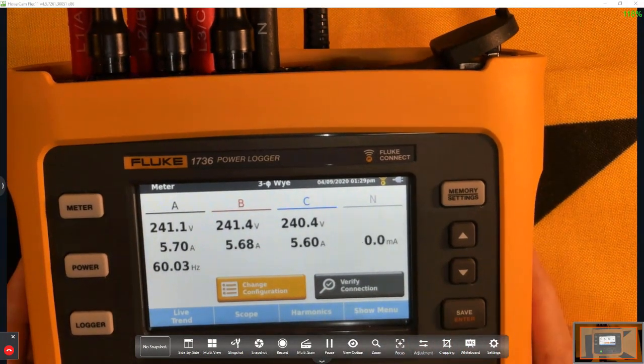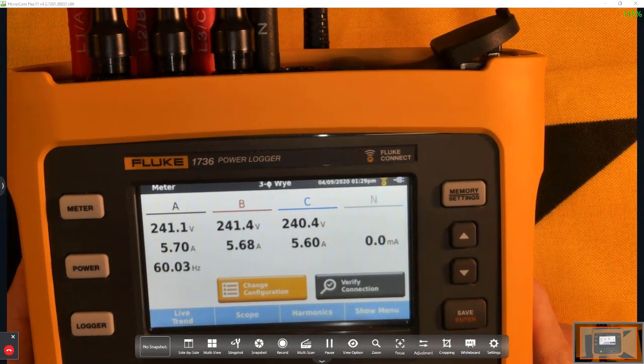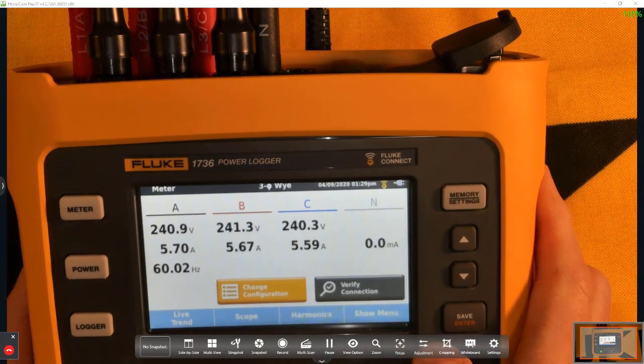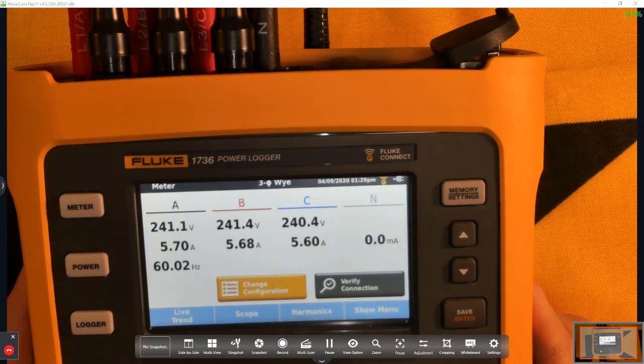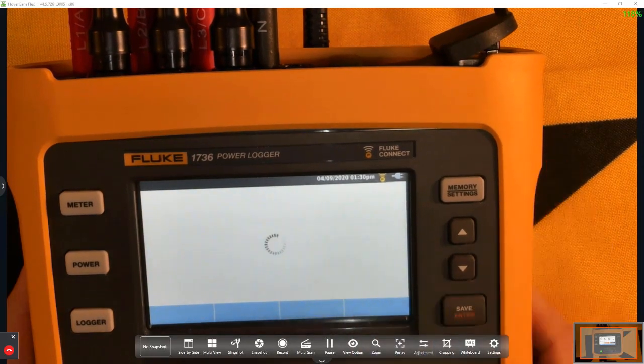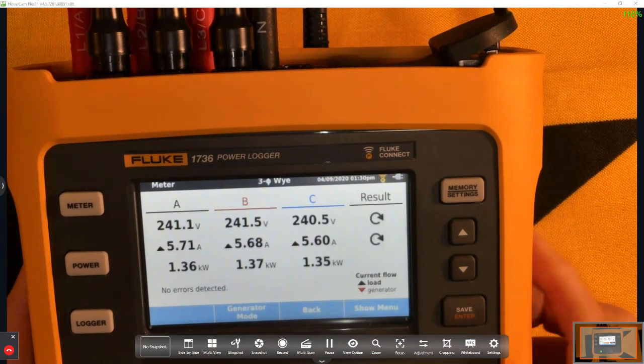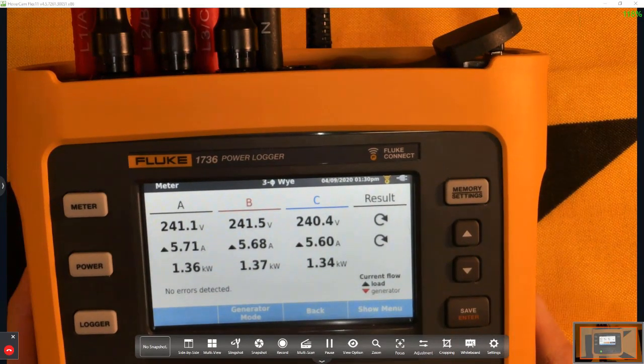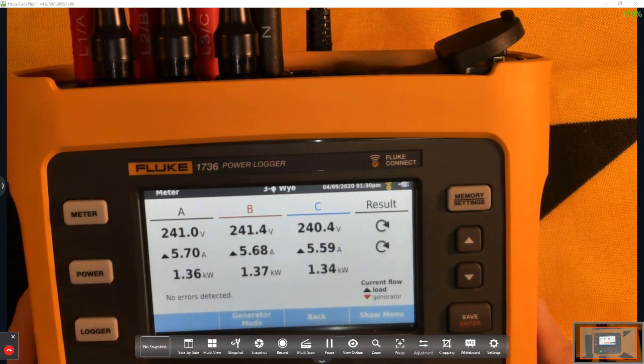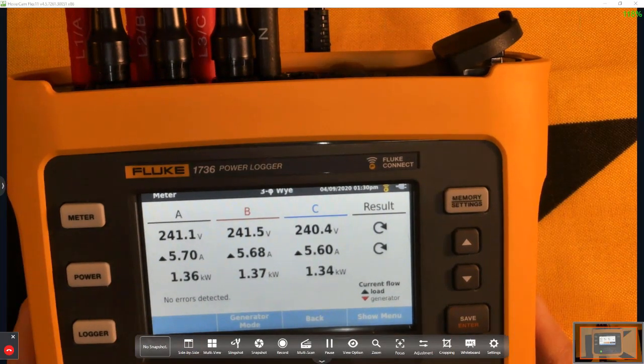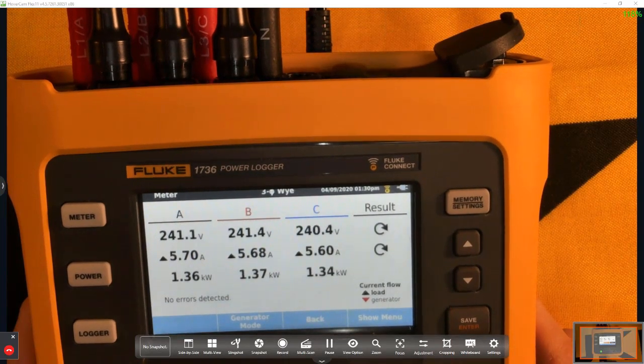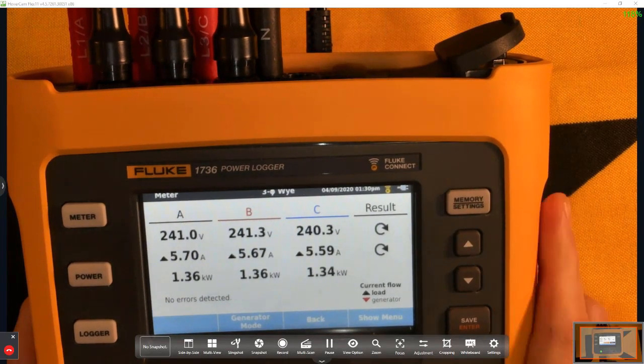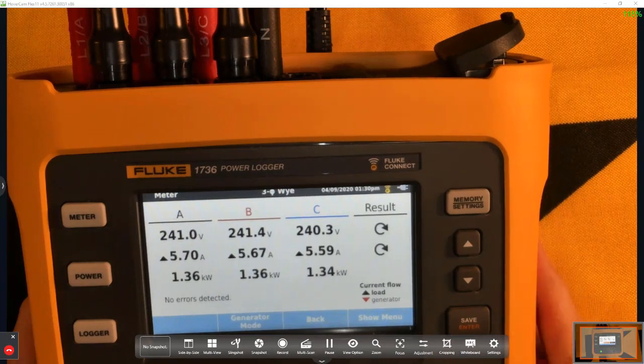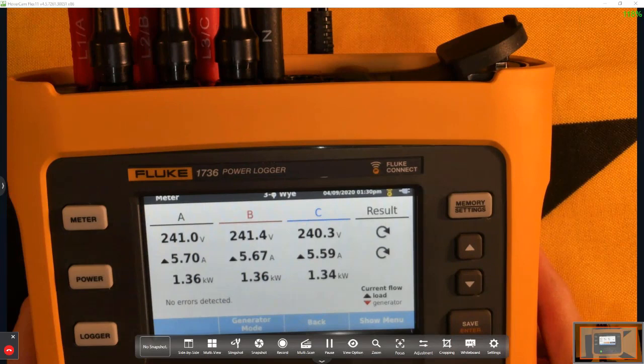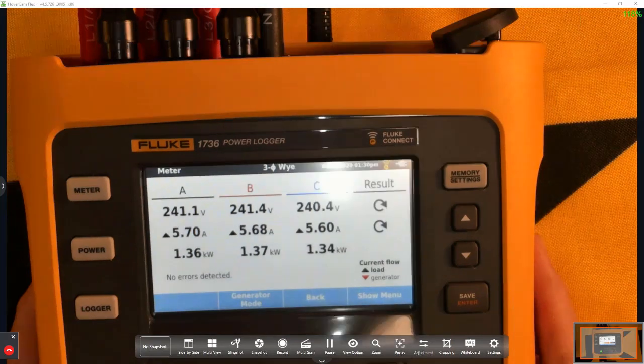With Verify Connection, we're trying to make things simpler—one issue we deal with regularly is customer miswiring. If you go to Verify Connection, the tool does a pre-check to let you know if there are any problems. In my case it says no errors detected because everything's configured correctly. But if errors are detected, you have the ability to have the meter try to correct the condition automatically, without adjusting any wiring, which makes this a really simple feature.